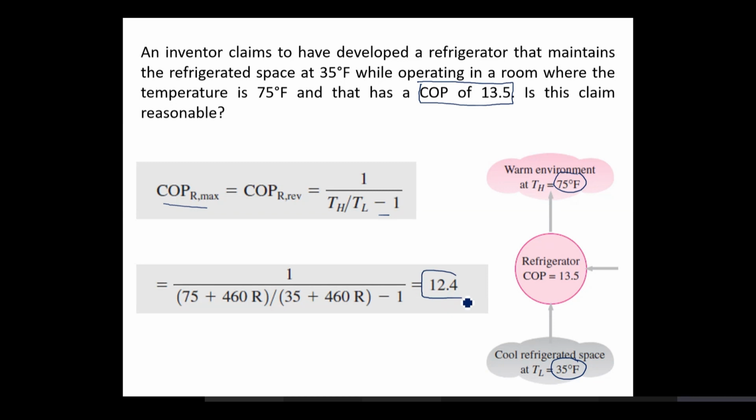So what do you think? Is it a reasonable claim or not? No, sir, not reasonable. Yes, it's not reasonable. Anything greater than 12.4 as a coefficient of performance is not possible.